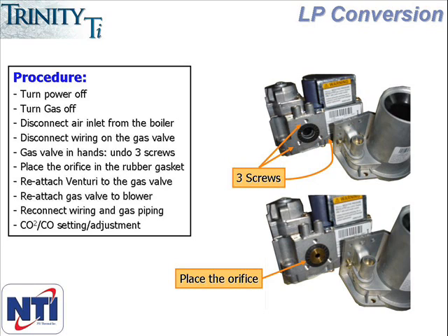This will allow you to remove the venturi from the gas valve and you will see a rubber gasket. Place the orifice in the rubber gasket and, taking care to make sure the gasket is properly placed, reattach the venturi with the three screws you previously removed.